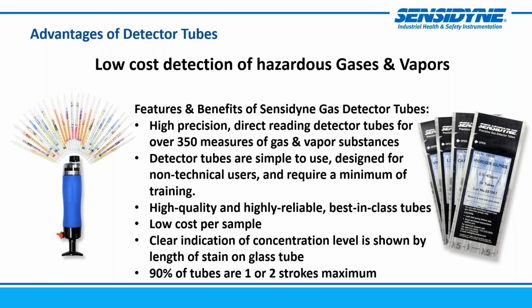Whereas when you use a gas detector tube, most of them have a 2-year shelf life. You can keep them on hand during that entire window and pull it out. You don't have to calibrate it. You can perform your leak check on your pump. You can perform a reading and get a reliable result right then and there. It can provide a clear indication of concentration level based on that length of stain on the glass tube. And again, 90% of tubes are either 1 or 2 strokes maximum, whereas with some other tube manufacturers and pump types, they could require multiple hand pump cycles or strokes. So really, we want to make this both fast, easy to use, reliable, and timely for use.